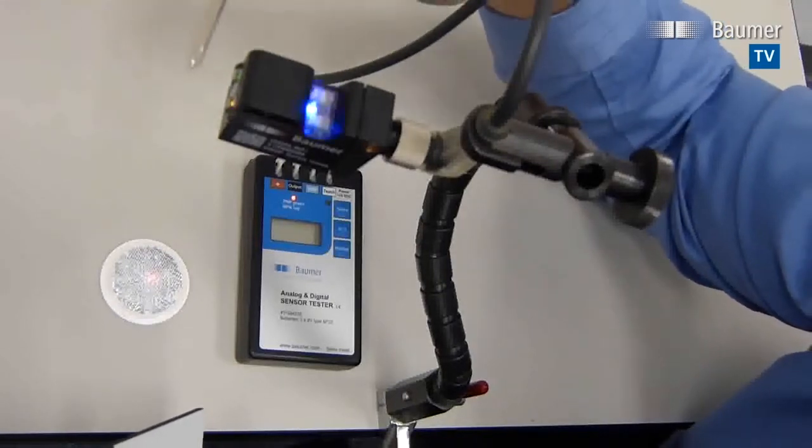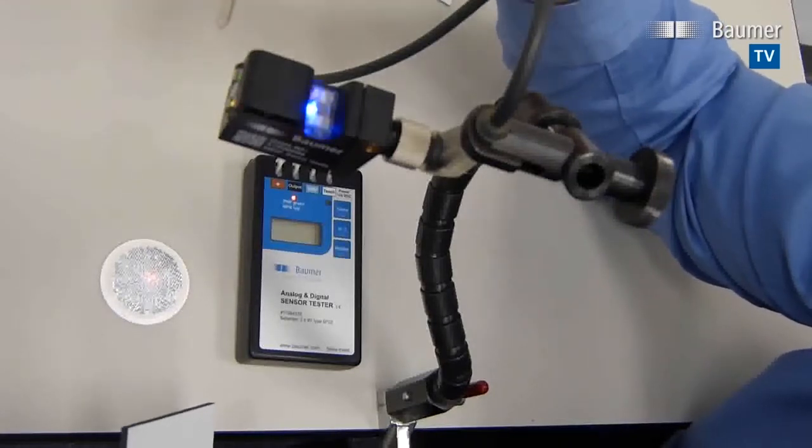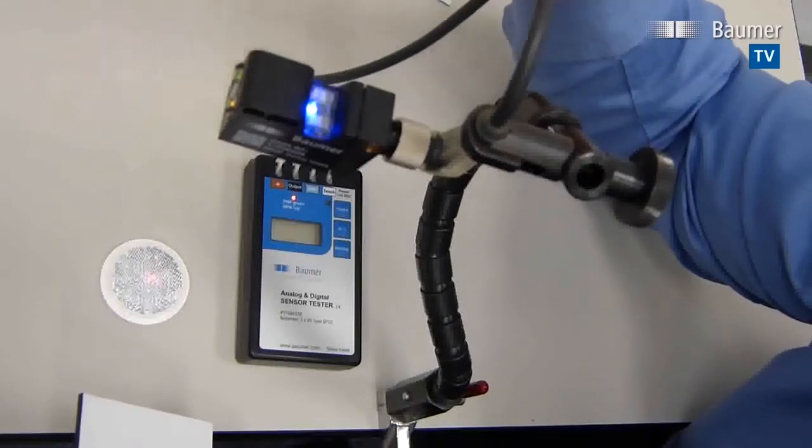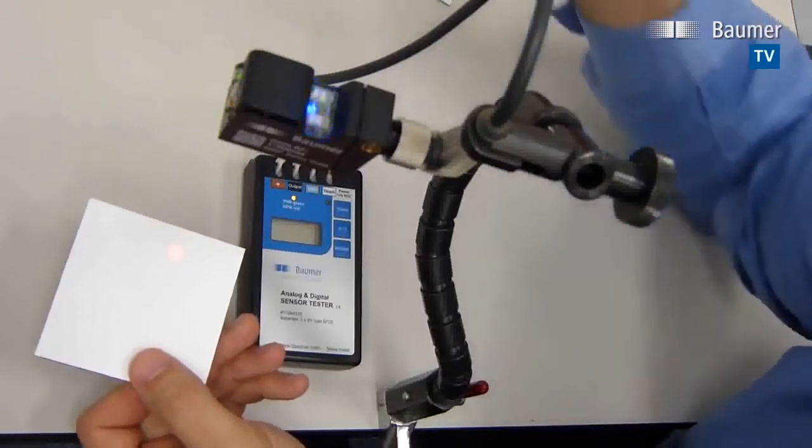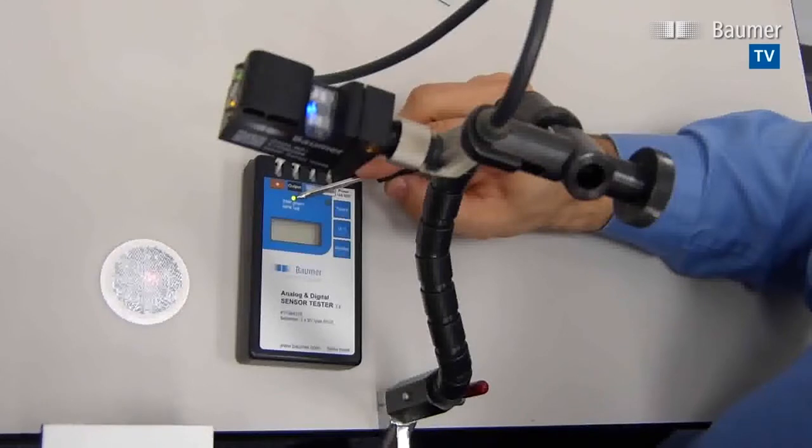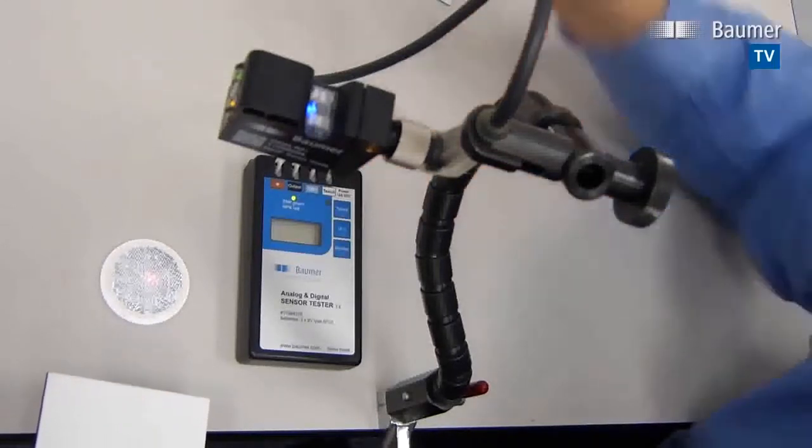Again, we get into level 1 teaching. We hold the QTeach until it flashes once per second. In this case, we can show it the reflector and then show it the object, and it'll change its light-dark-operate status. Here, there's a green light, which indicates that there's a PNP output when there's no object.